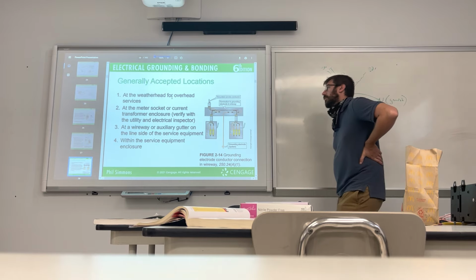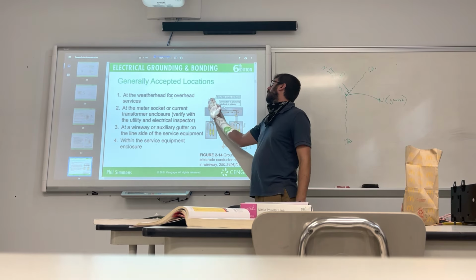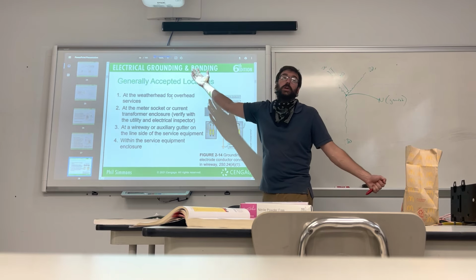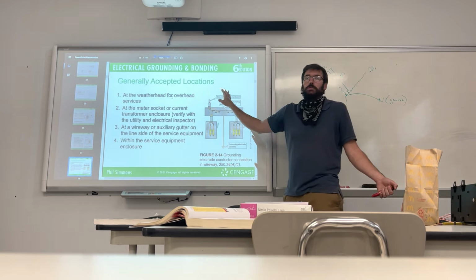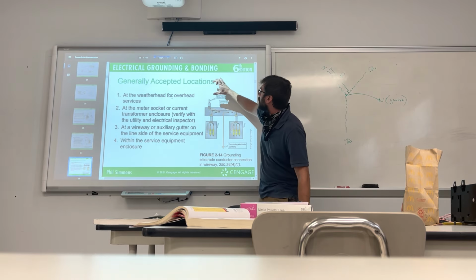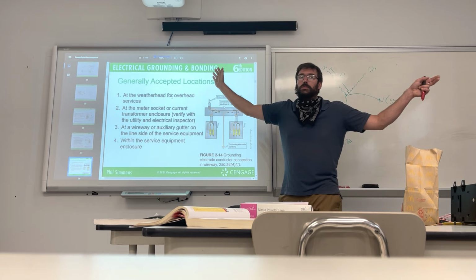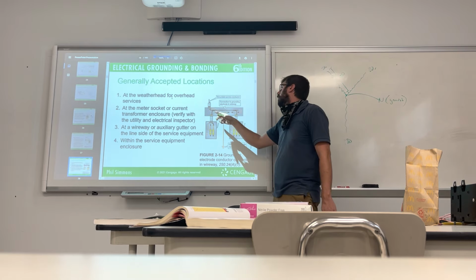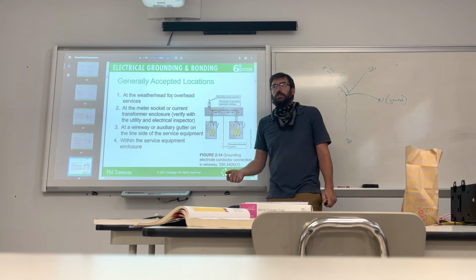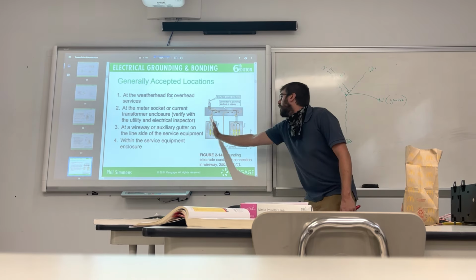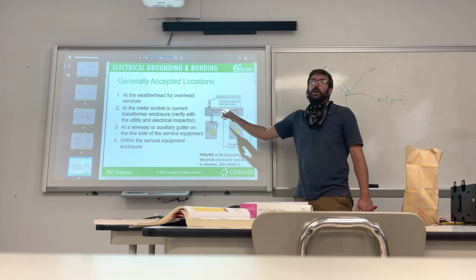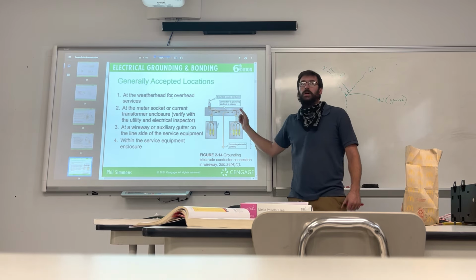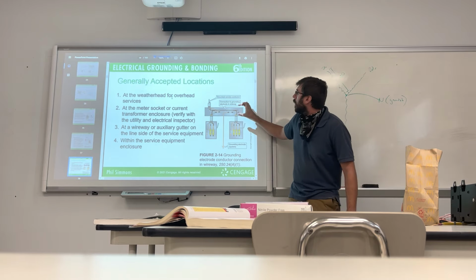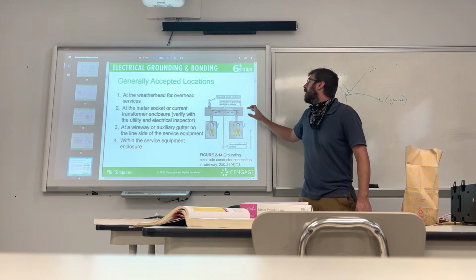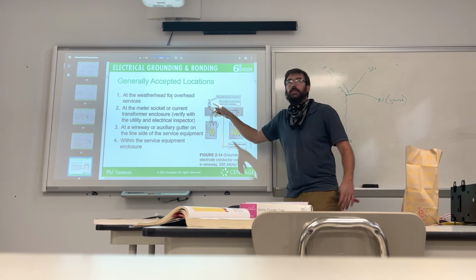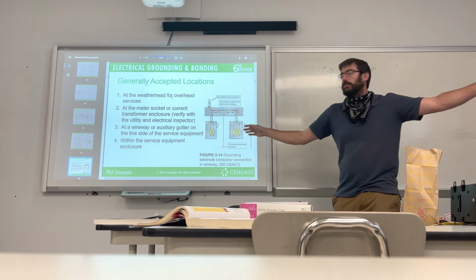So this is kind of odd, right? The line coming up here could be going to a weatherhead, or it could be coming off the meter. It could be both. Who knows? Because I don't see a meter here. The meter could be right here, or this could be directly to the weatherhead. But now, coming into a bus bar, which is just like a terminal block that I was talking about in the last class, both of these are given an even shot at that power, right? They both have an even chance of getting that power up there. Do they or do they not? There is no metering device. There is no overcurrent protection. If there's 200 amps coming in, there's 200 amps right there. Am I right? Am I wrong? Okay, I'm right. I'm always right.